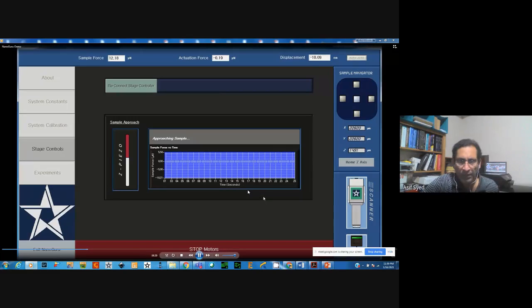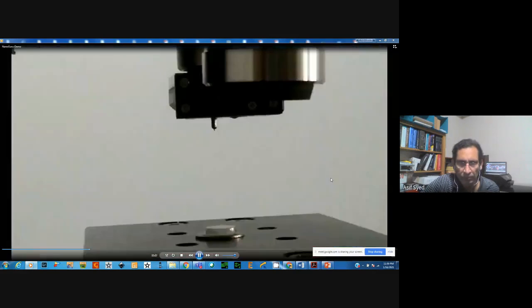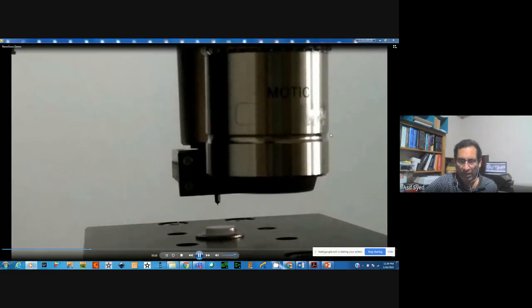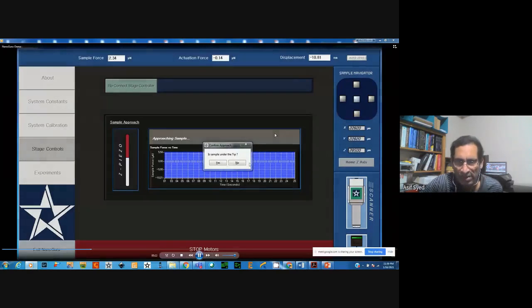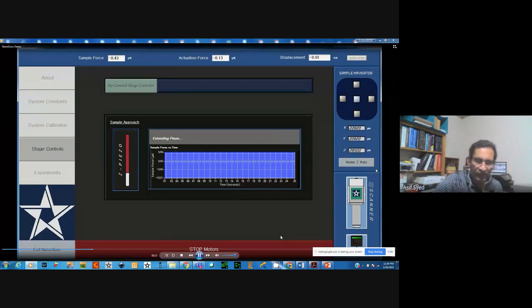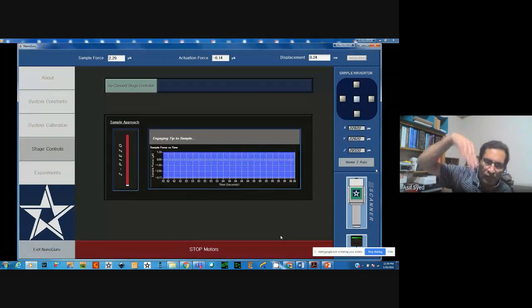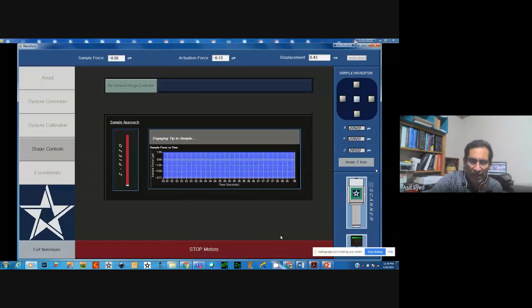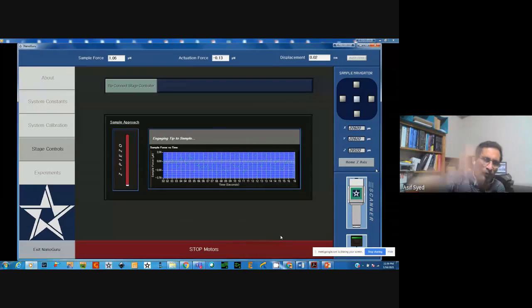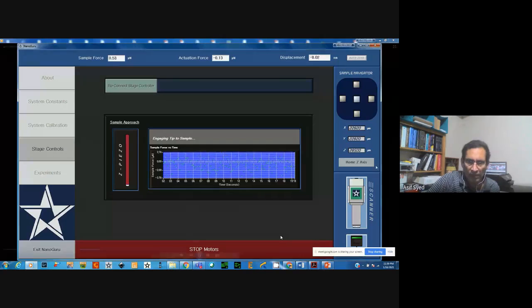Okay, it will take a few seconds. Okay, you can see that it came back closer to the surface. It is asking whether it is underneath the tip. I say yes. Now the piezo will extend, and the transducer is stepping towards the sample surface. Okay, you can see the sample force, and I asked for 2 micronewton. When it consistently measures the 2 micronewton force, you can see the piezo will pull back. Okay.